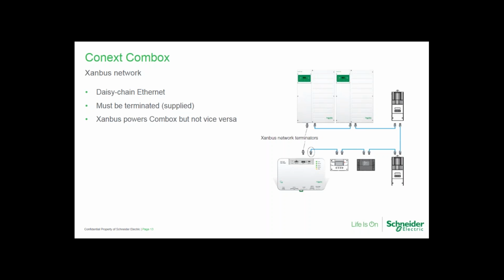The Xanbus network is simply a daisy chain of devices using Ethernet cables. Each device has two Xanbus ports, so there will always be an open port at either end of the network that must be terminated. Each device ships with a network terminator. The XW Plus, Conext SW, and MPPT-80 are the only devices that supply Xanbus power. Xanbus will power the ComBox, but the ComBox cannot power Xanbus, even with the AC adapter.